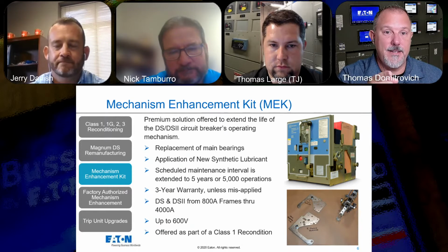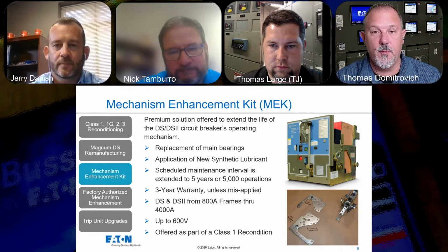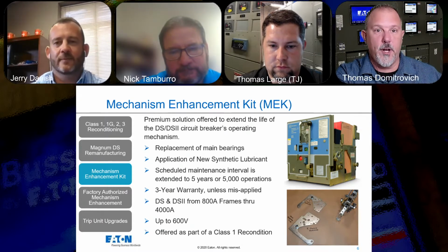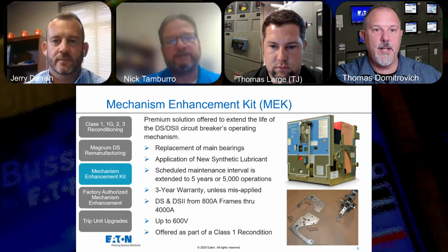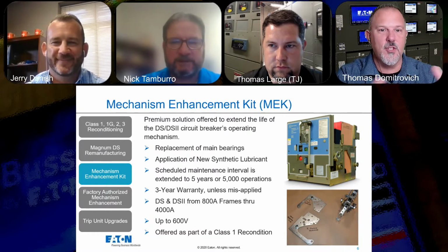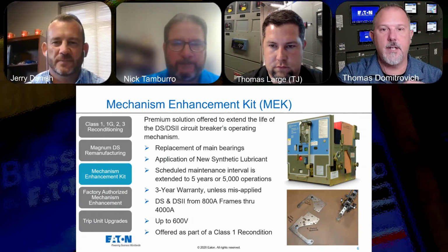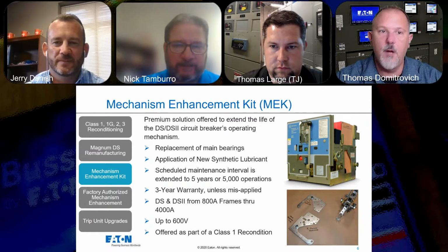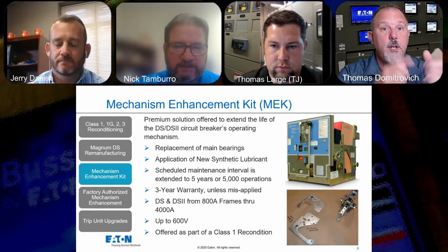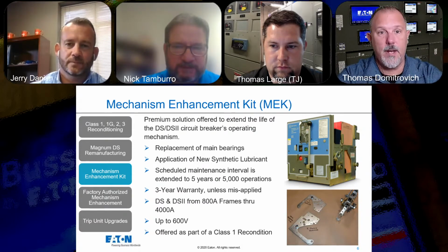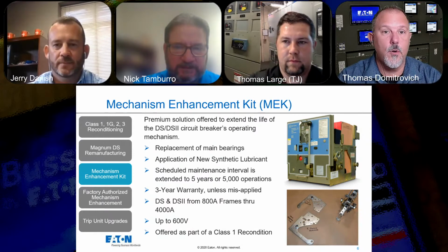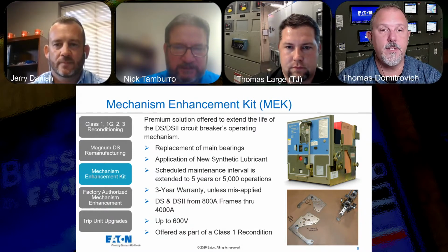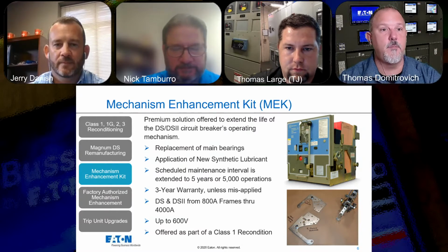To Nick or TJ's point, we take these older breakers, like barn finds. You find something salvageable, get it up to Nick and TJ, and they tear it all the way down to a Class 1, bring it back up shiny, then ship it down to the plant. Then they can do a planned swap, put the new one in, take the old one out, do a Class 3 on it, or even a complete overhaul, and now you're cycling breakers through your facility.